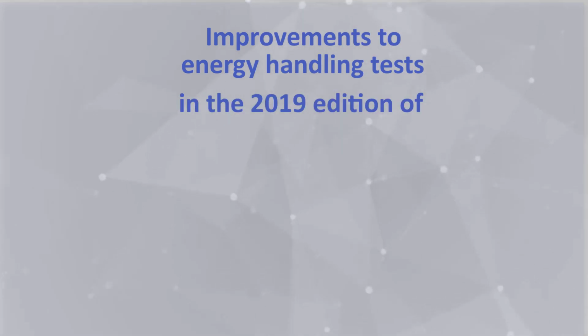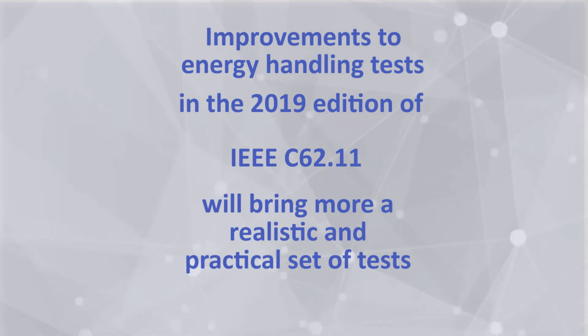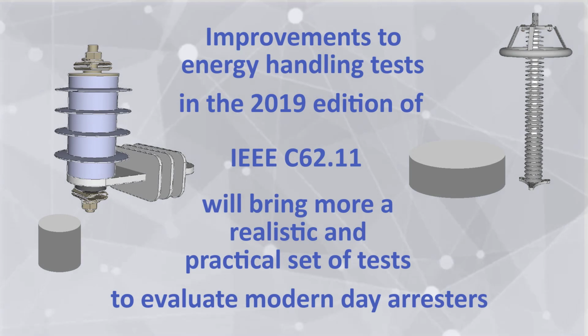The improvements to the energy handling test in the 2019 edition of IEEE C62.11 will bring a more realistic and a more practical set of tests to assess modern MOV arrestors.